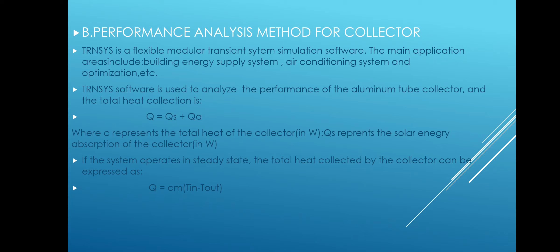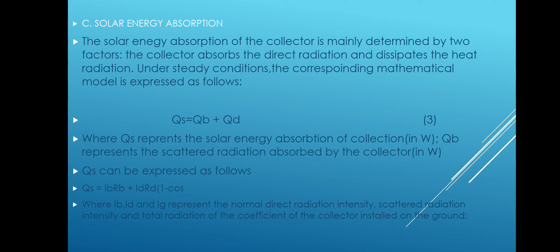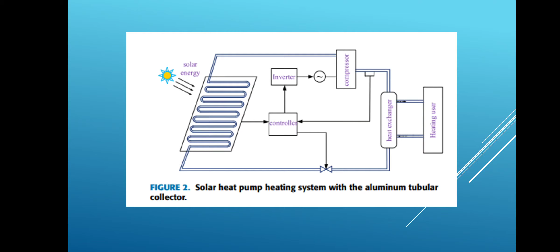Under steady conditions, the corresponding mathematical model is expressed as follows: Qs = Qb + Qd, where Qs represents the solar energy absorption of the collector in W. Qd represents the scattered radiation absorbed by the collector in W. Qs can be expressed as follows: Qs = Ib Rb + Id Rd (1 - cos theta), where Ib and Id represent the normal direct radiation intensity and scattered radiation intensity, and Ig the total radiation coefficient of the collector installed on the ground. This picture shows the solar heat pump heating system with aluminum tubular collector.